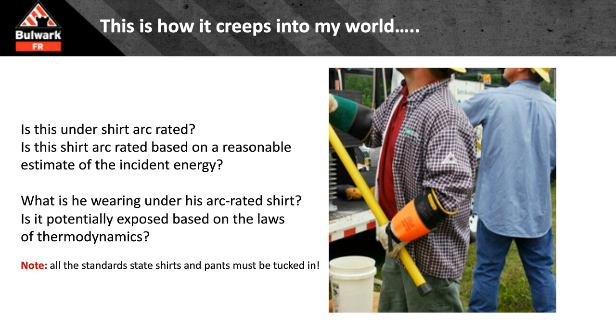Here we have PPE deployed in the field. What could go wrong here? Is this shirt underneath his arc-rated shirt, is it also arc-rated? Because now it's exposed. So it has to be equal to or greater than the potential incident energy he may receive in an arc flash, because now that's technically the outermost layer.